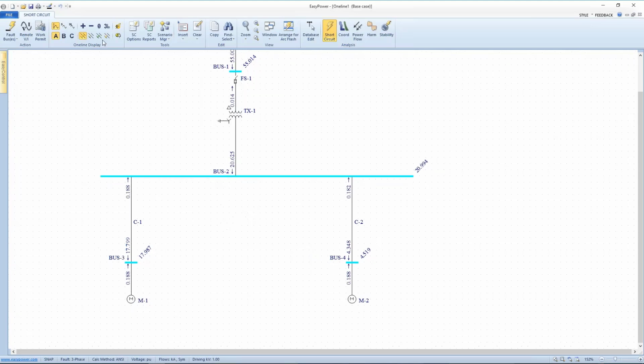So for now, we're looking at motor contribution back on the half cycle three-phase fault, faulted all the buses. And so now we see 20,625 amps supplied from the utility and 182 amps supplied from each of these motors. So that means this bus better be rated to handle 21,000 amps at a minimum. So this all looked normal. He said, okay, that looks fine. Now let's calculate incident energy.